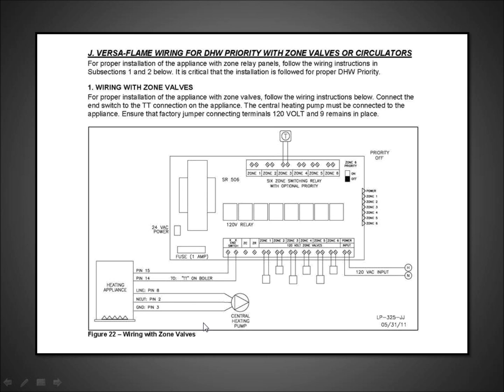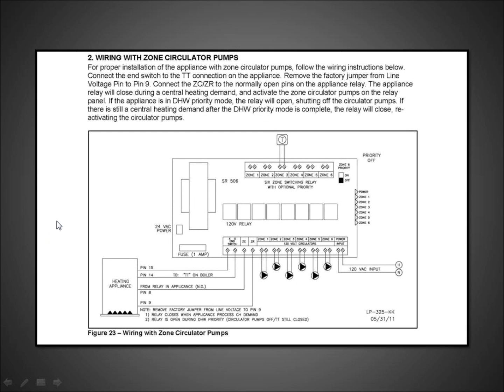That's for zone valves. For pumps, what we're doing is we're now going into the ZRZC. We have a dry set of contacts where the jumper was. So you'd remove the factory jumper from the line voltage to pin 9. You note there's 2 notes here. 1, relay closes when appliance process central heating demand. Okay, so when there's a central heating demand, we will power up the pumps for the central heating loops.